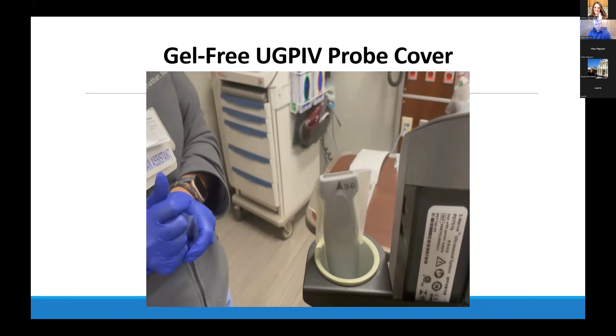Placing that stretched over that foot is perfect for a clear vision for the ultrasound screen. So some people say, well, oh Matt, why don't you just use a TSM? Well, when you look at the manufacturer's instructions for use, it says do not apply adhesive film such as Tegaderm to transducer lenses. Why is that? Because it can damage the lens.